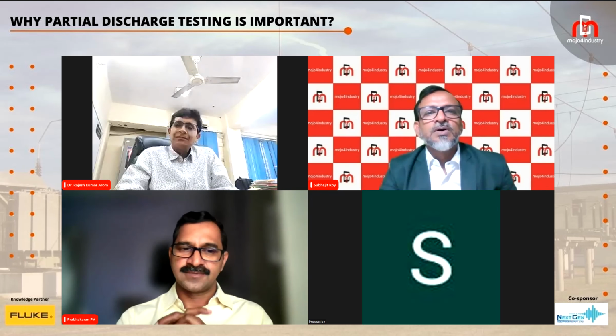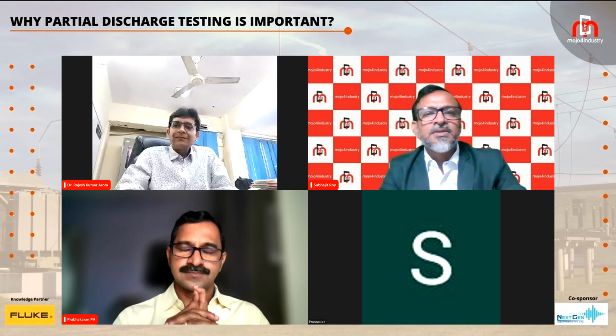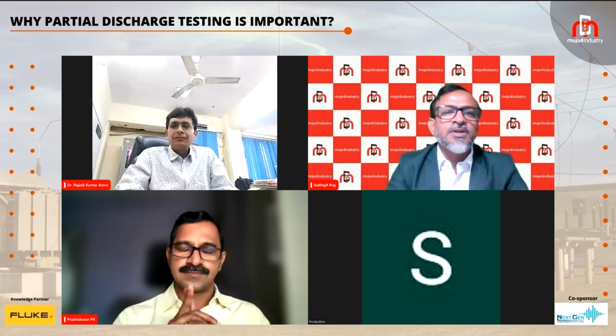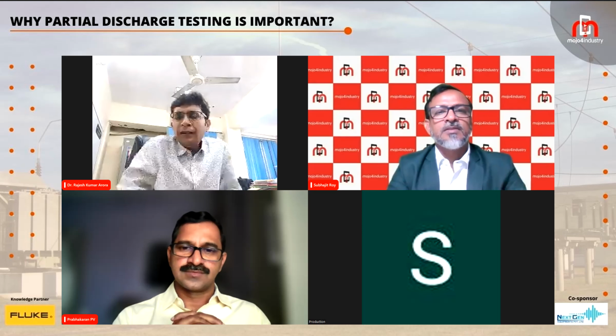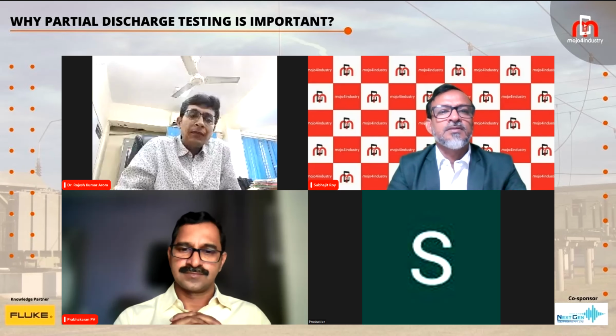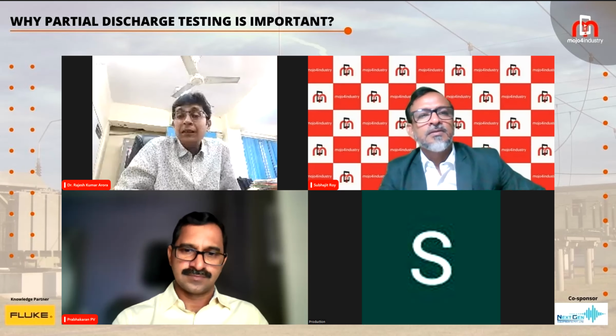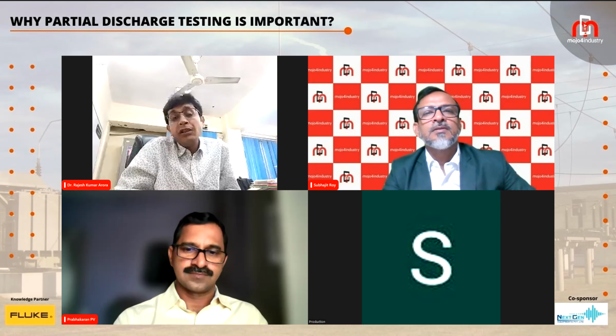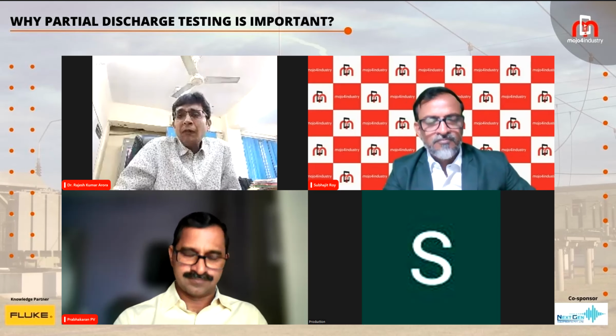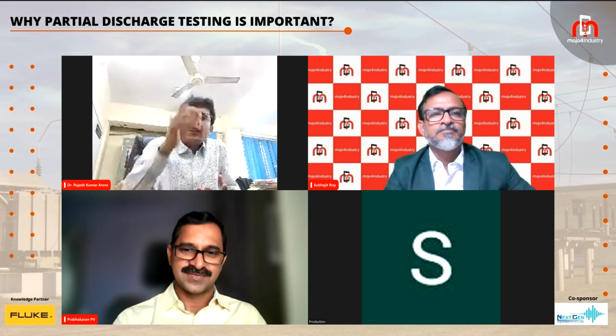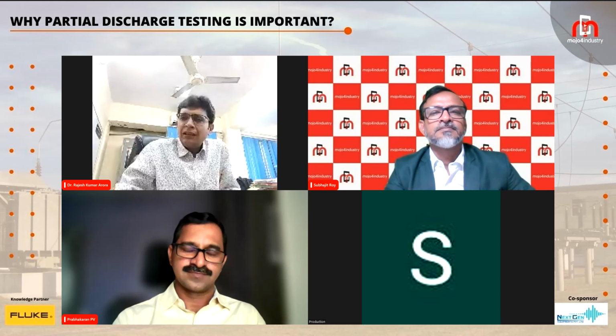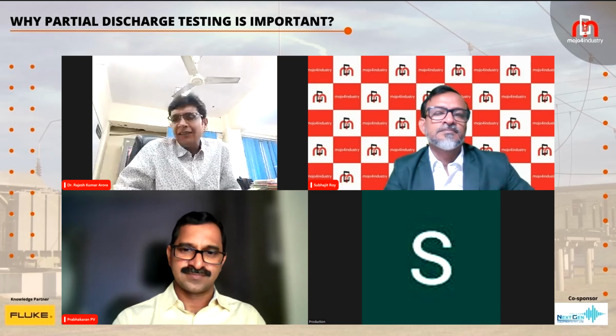Divyang Raval is asking which are the various types of sensors used to detect partial discharge. We have some inbuilt sensors given by the manufacturers of GIS. Sometimes we use external sensors, and sometimes we use a CT, a high frequency CT, around the cable termination and cable to get the PD pattern.